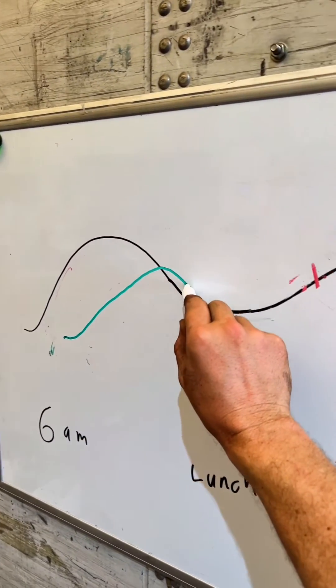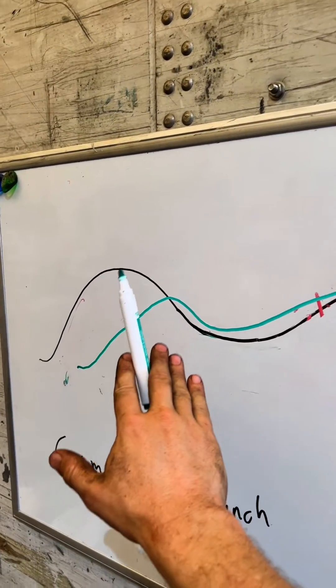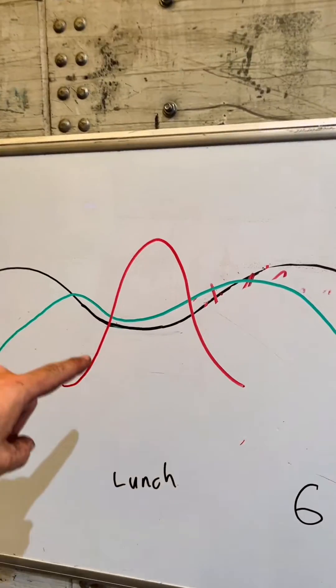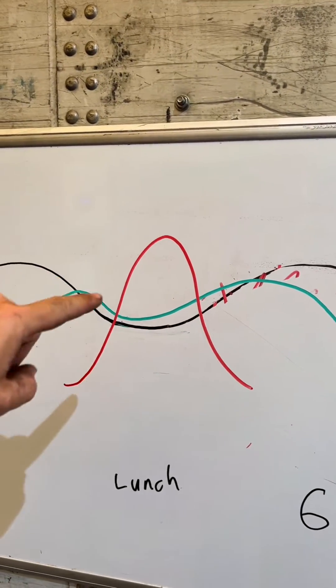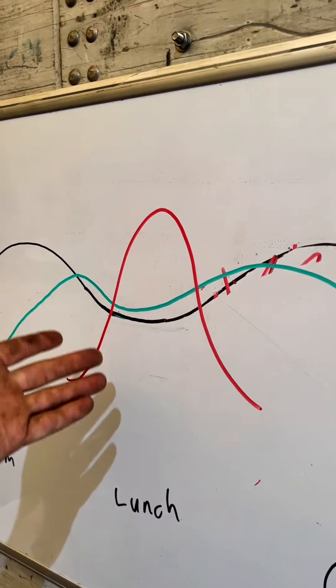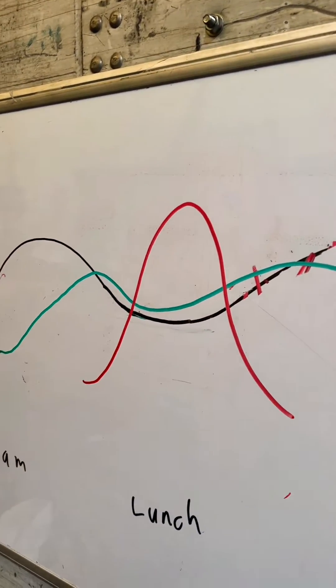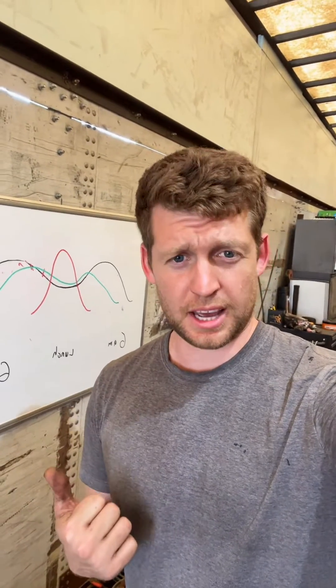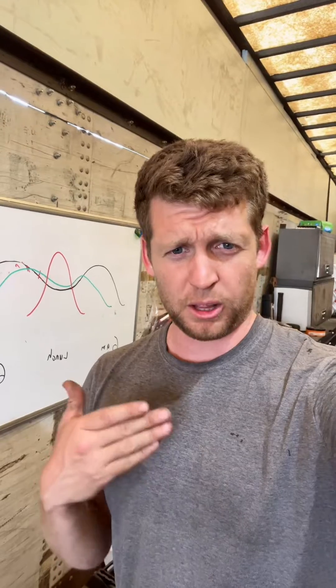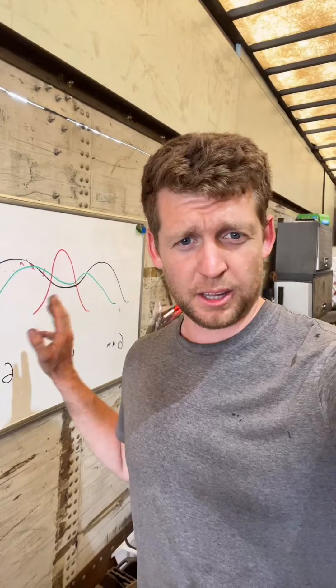The power curve for east-west orientation looks a lot more like this. That east sun, as it rises in the morning, is hitting the panels. It drops a little bit in the day, and then it comes back in the evening. Your peak power output is less in an east-west than in south-facing, but it's more spread out through the day. With a south-facing array, you get more power, but that also means more battery storage and larger inverters. Going east-west means you can run a smaller battery setup and smaller inverters — it's cheaper because you're not hitting a peak output the inverter has to handle. It handles a lower, smoother power.